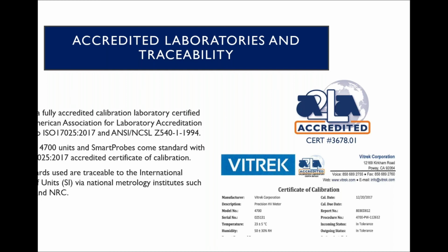So Vitrek is a fully accredited calibration lab. We are certified by A2LA to ISO 17025-2017 and ANSI NCSL Z540-1-1994. So it really is important to establish and maintain a documented path of traceability. It may be just as important to do so as it is to identify all of your other sources, as you may be able to state that you have a perfect calibration, but if you're not traceable back to the international system of units, then your perfect calibration could yield a very different result from another laboratory. So all standards that Vitrek uses are fully traceable back to the SI via national metrology institutes such as NIST and NRC through a documented path.